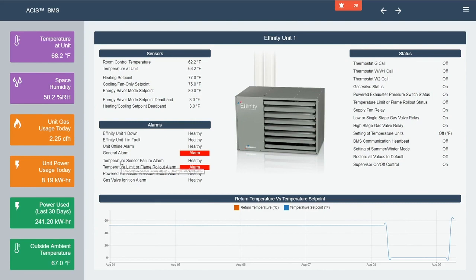Also from here you have the valve statuses and the fan statuses, so now you can start looking at how long the unit's been running and how long the gas valves have been on. So you may find that one of your units in the space has been running for 15 hours and another unit has only been running for 5 hours. And what you might find is that one of the vent systems has been stuck open, which is allowing cold air into the space. Because you notice this from the interface, you can now go and fix that problem rather than having to wait until you have an issue with temperature in the space.